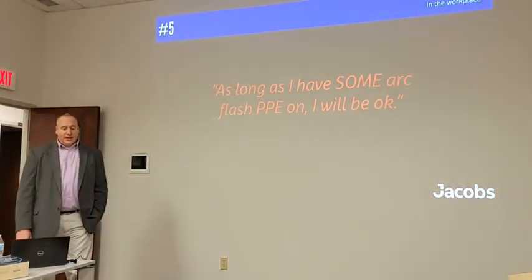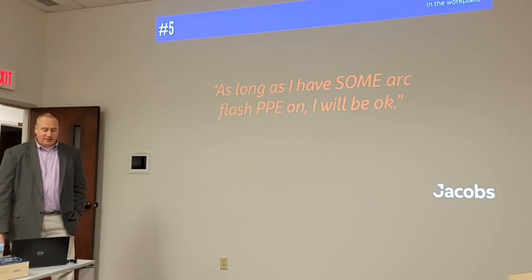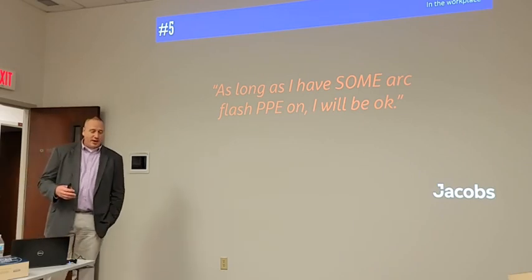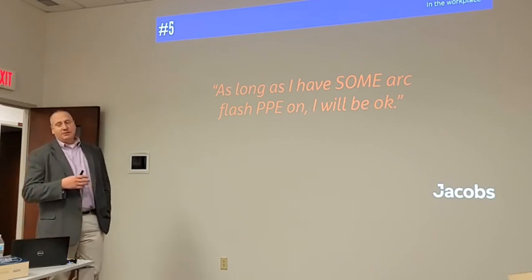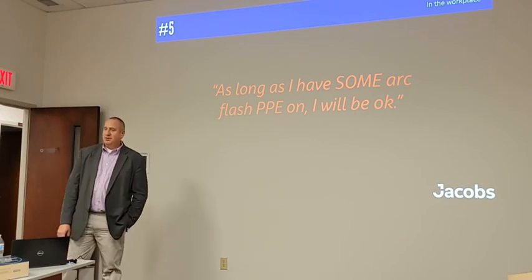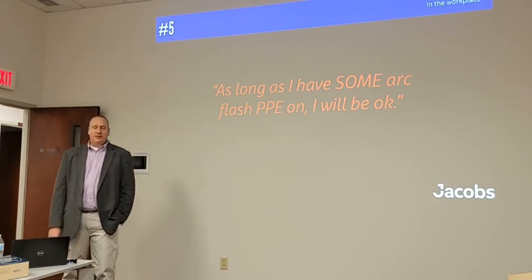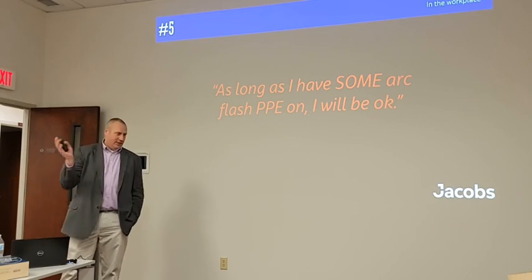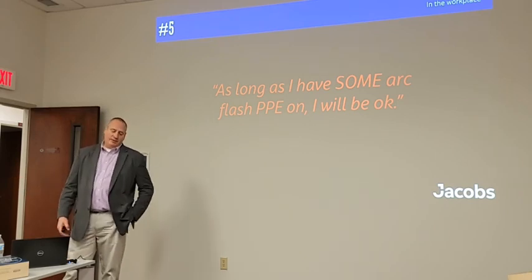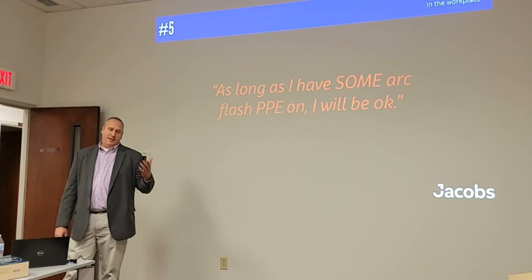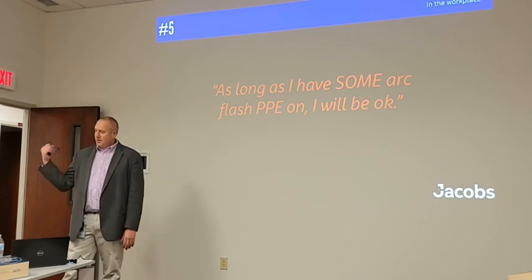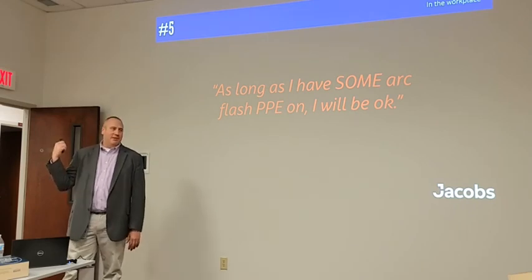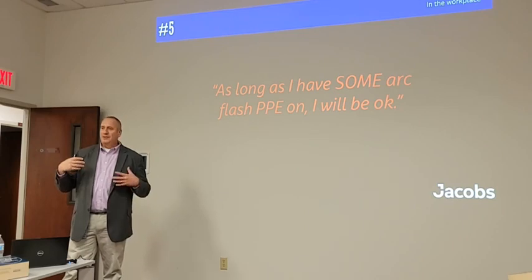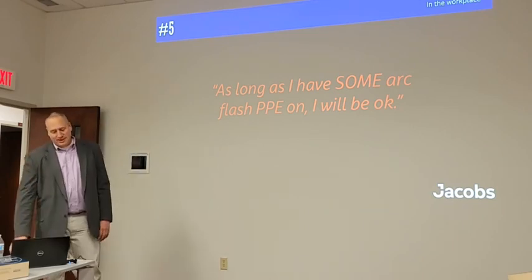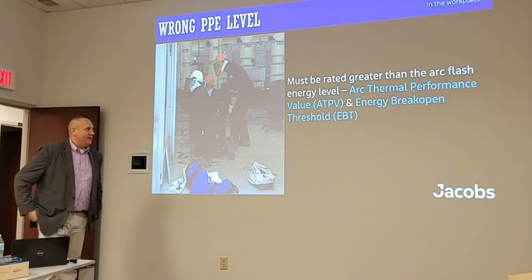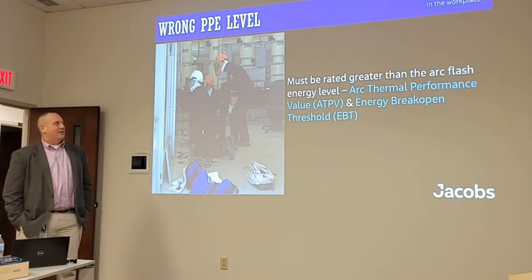So the next one: as long as I have some arc flash PPE on, then I'll be okay. And this becomes more common in facilities where you have to travel distance. I see a lot with utility companies where the utility worker leaves the shop, has to drive somewhere and gets there and realizes, I've got my category 2 PPE, but what I need here is category 4. I don't want to have to drive 15 minutes all the way back to the shop just to get my category 4 suit. I'll just wear my category 2, it's better than nothing, right? Well, that's not true. Your outer layer has to be rated greater than the arc flash energy level.